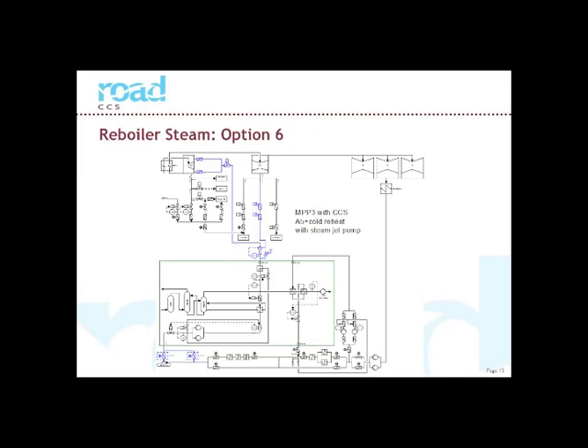Therefore, we plan to install a so-called steam jet booster. The driving steam for this steam jet booster comes from the outlet of the high pressure turbine. It will increase the pressure to the desired level. The pressure of the low pressure steam we will extract all the time. Condensate will be pumped back to the condensate system of the power plant. You see at the bottom side of this slide. And furthermore, condensate is used for some cooling of the CO2 leaving the stripper in the capture plant. We also come back to that later.